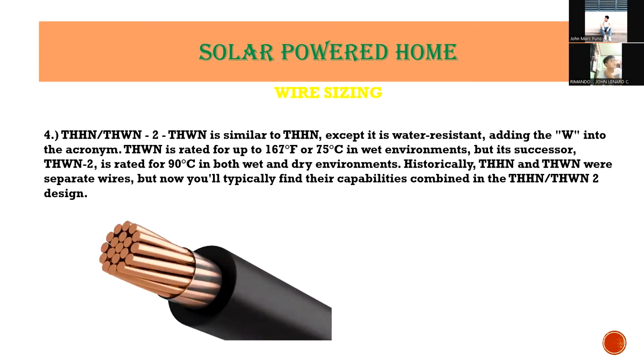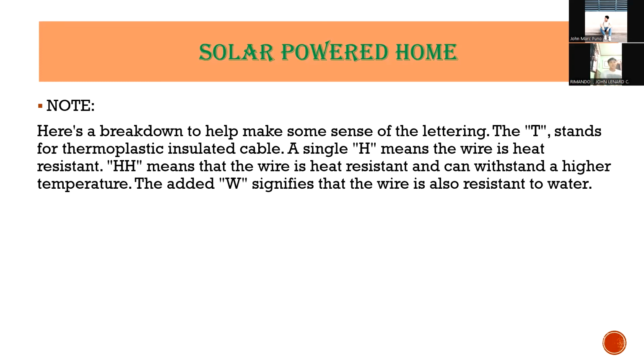So number 4, THHN or THWN. THWN is similar to THHN except it is water resistant. So yun nga po yung pinagkaiba nila. Yan po ay water resistant. Adding the W into the acronym, THWN is rated for up to 167 Fahrenheit or 75 Celsius in wet environments, but its successor THWN-2 is rated for 90 Celsius in both wet and dry environments. Historically, THHN and THWN were separate wires, but now you'll typically find their capabilities combined in the THHN and THWN-2 design.